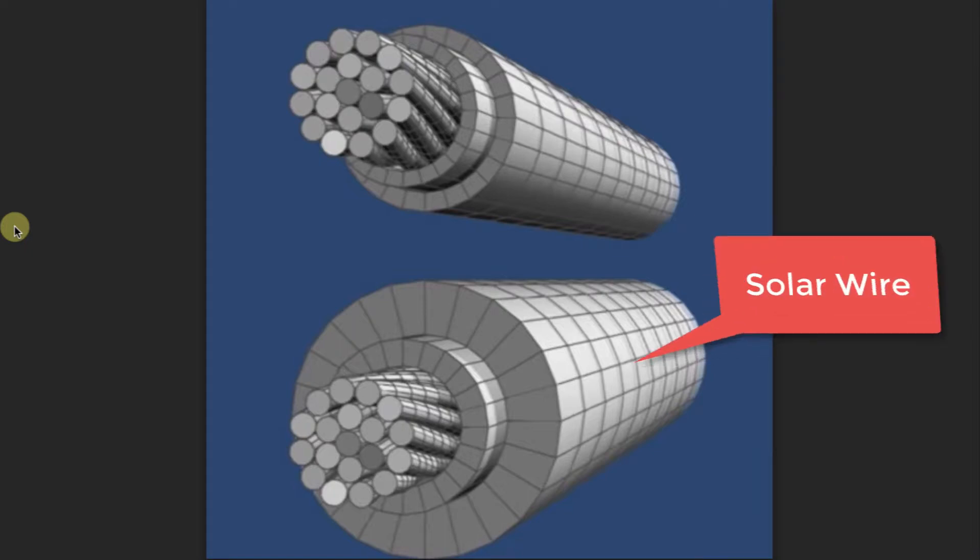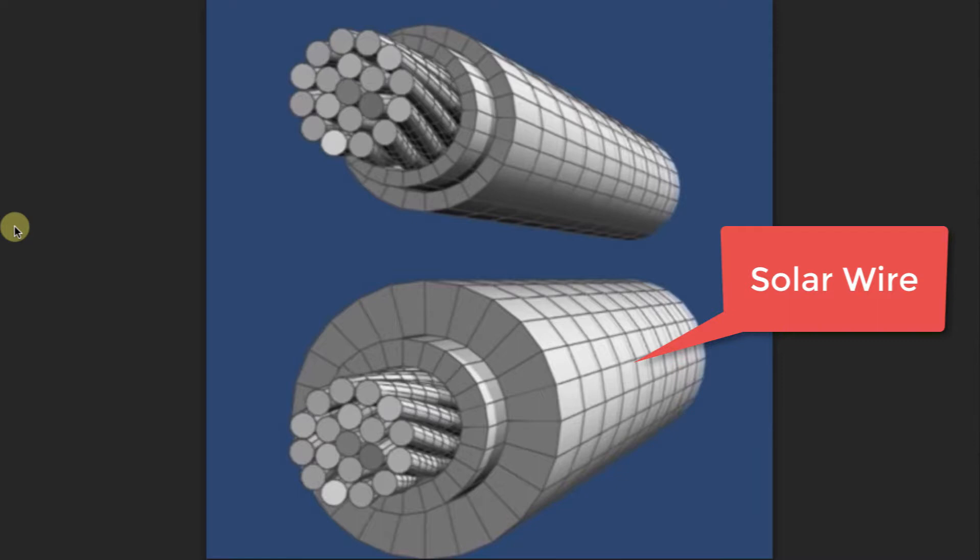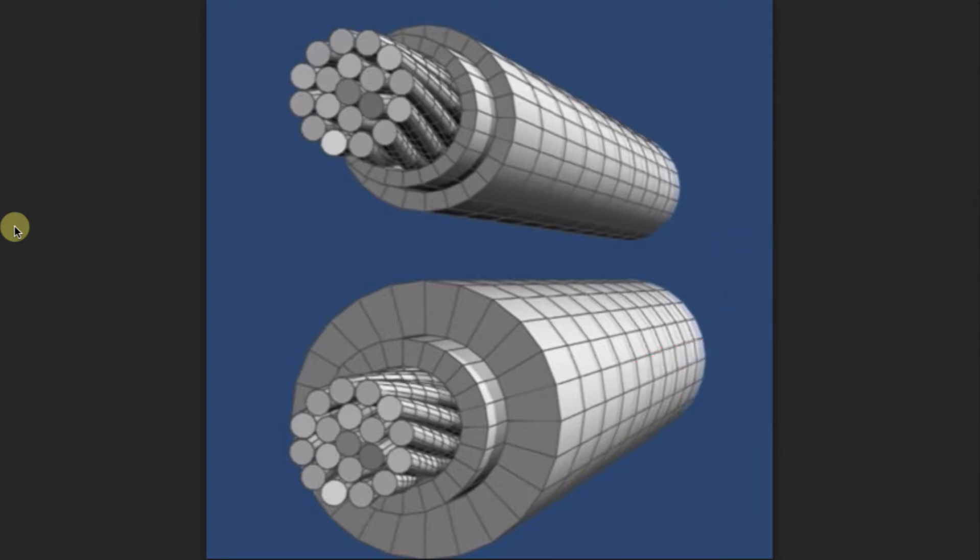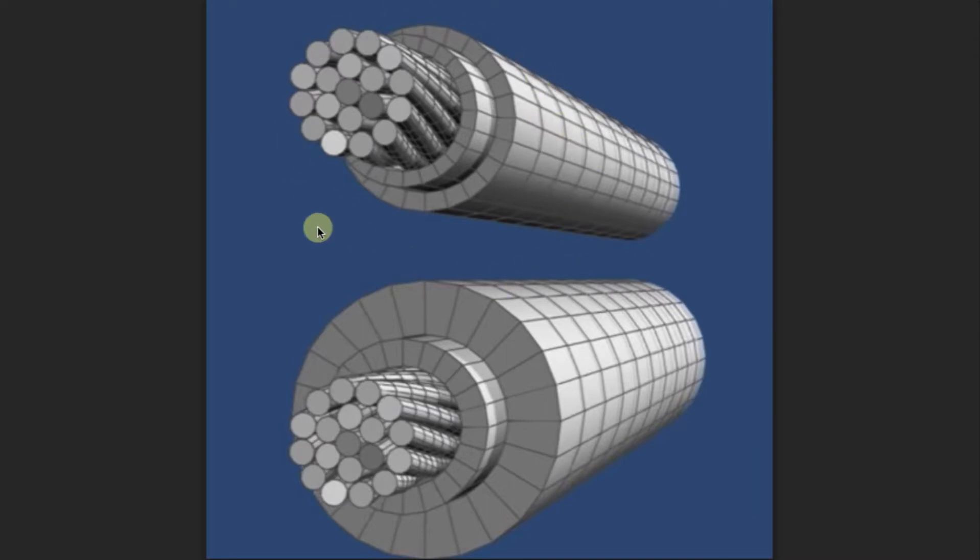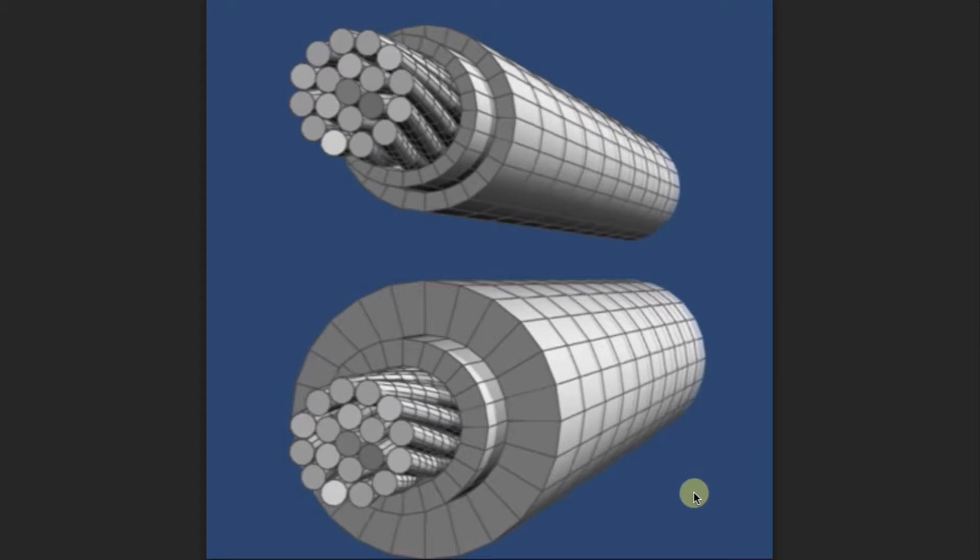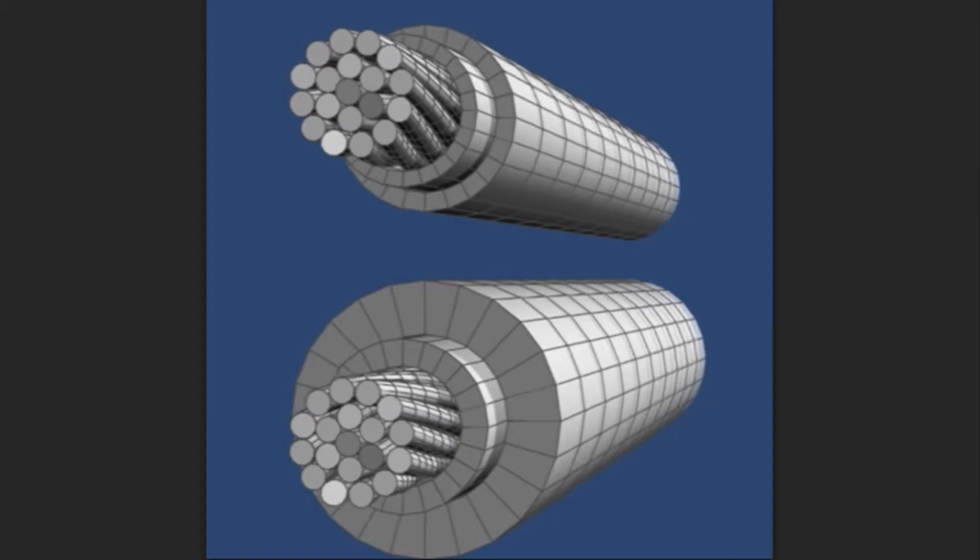And then down below is the thicker solar wire, which is now commonly used by most folks. But according to the latest NEC code, you can use both in making your jumpers and wiring up your arrays. So you've got to be careful though because if your clip is designed to hold USE-2 type diameters, and then you try and cram in a solar wire into that same clip, it's not going to hold it as well. It's going to open up too wide and it may eventually let go of that wire. So the solar wire is much thicker and you've got to choose clips that are specifically designed to hold that big diameter of solar wire.